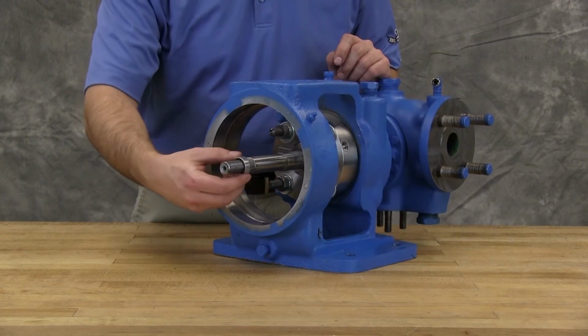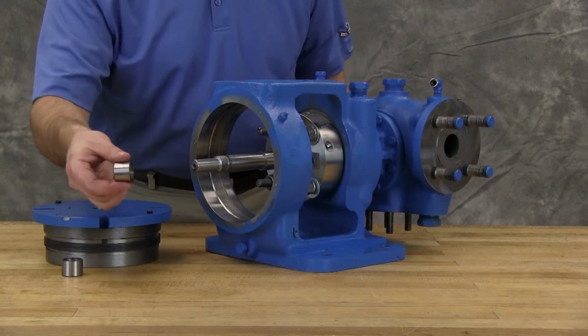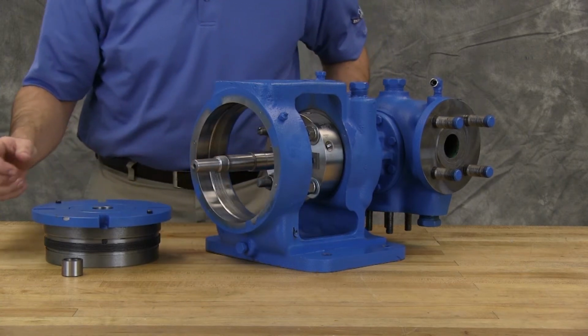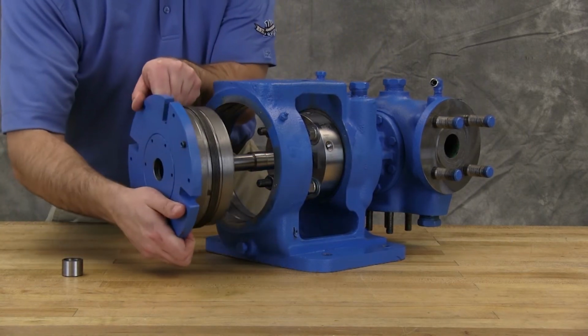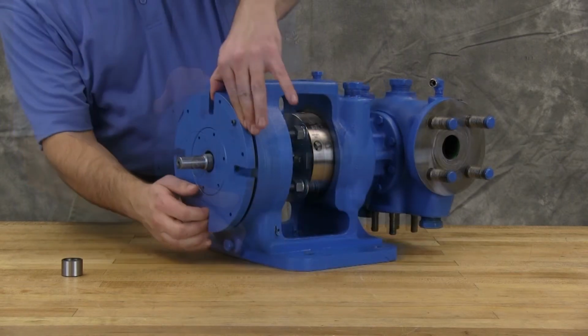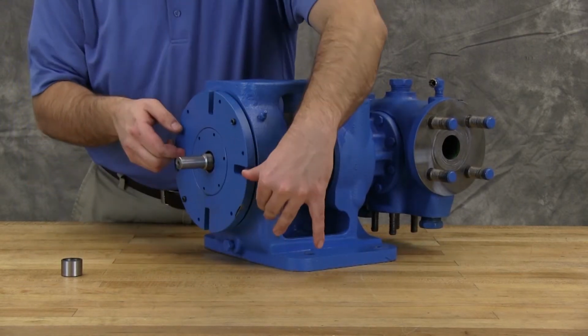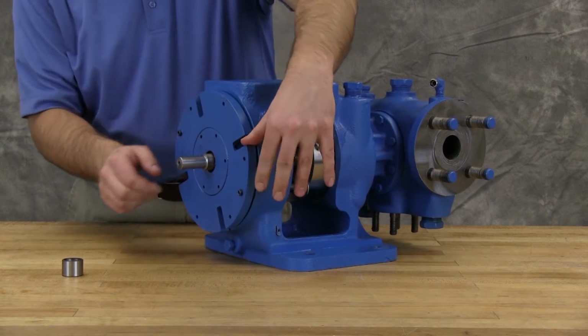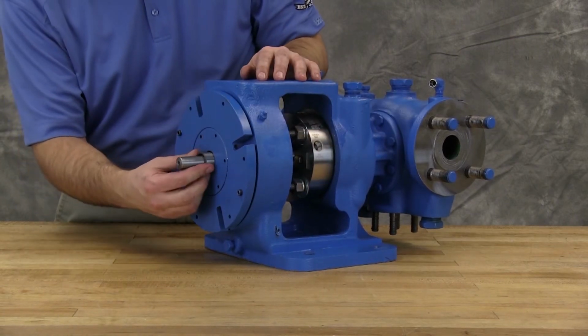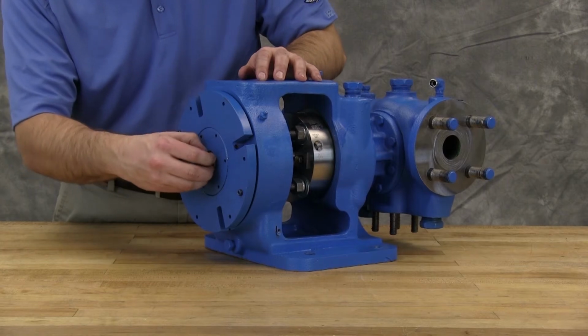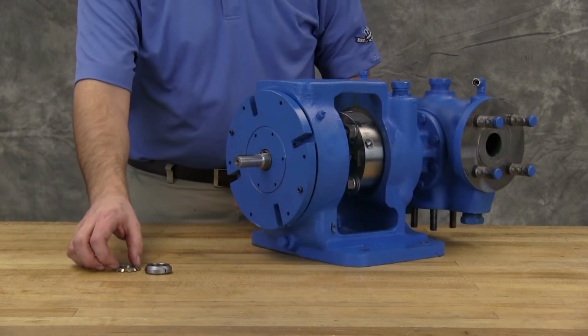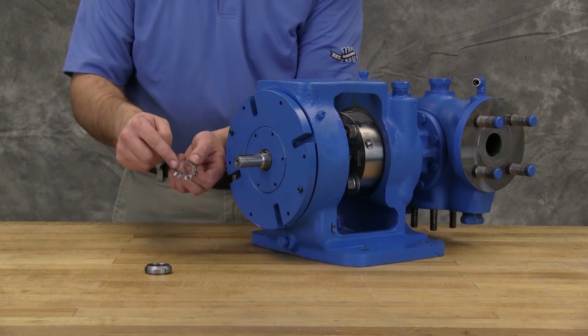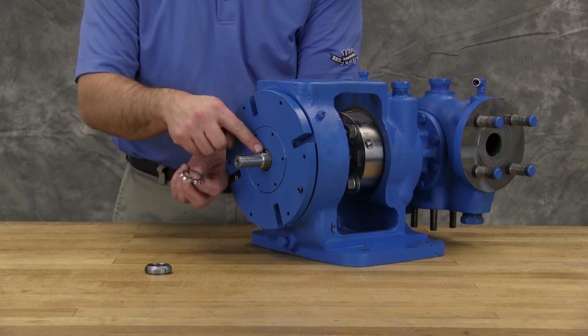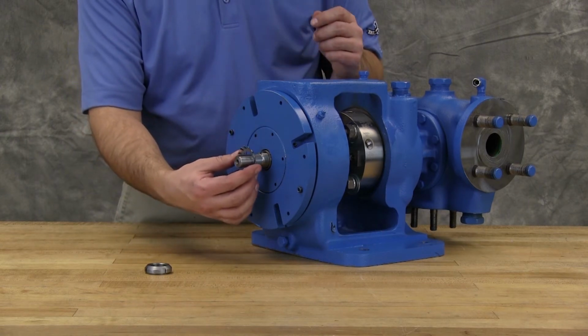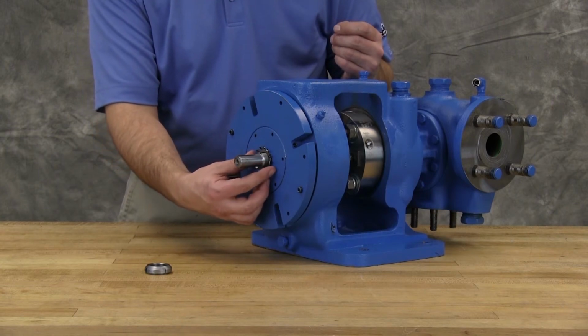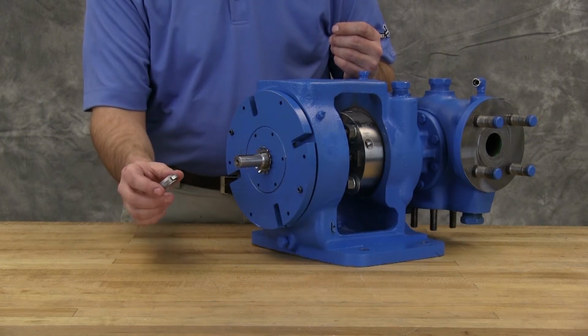Remove the seal installation sleeve. Slide the inner spacer collar over the shaft with the recessed end facing the head of the pump. Install the bearing housing. Install the outer bearing spacer collar. The tang of the lock washer goes into the groove of the shaft. Install the lock washer and lock nut on the shaft.